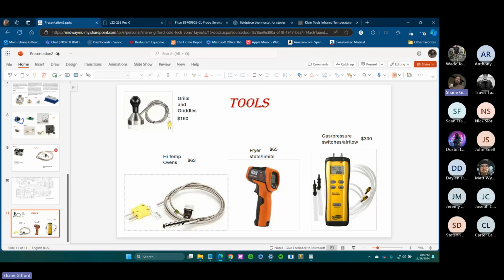And I actually picked this one up off Amazon too. This one's good, I believe, up to 800 degrees Fahrenheit. And it hooks right up to my Fieldpiece meter. This one's rated. I mean, it's metal jacketed. This thing is built to pick up those high temperatures. So if you're working on a small oven or a toaster heater or something like that, and you want to confirm what your temperature is, you can throw one of these in there, rest it on the rack. In fact, it comes with an alligator clip, there it is right there. You can clip it to an oven rack, somewhere in the middle.